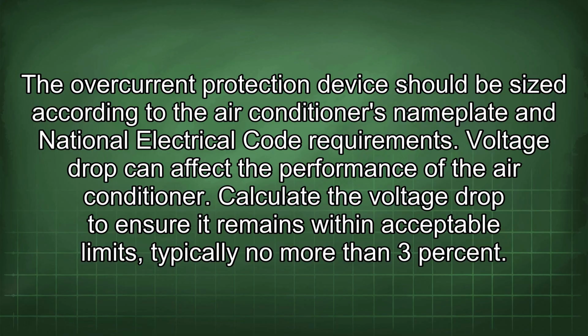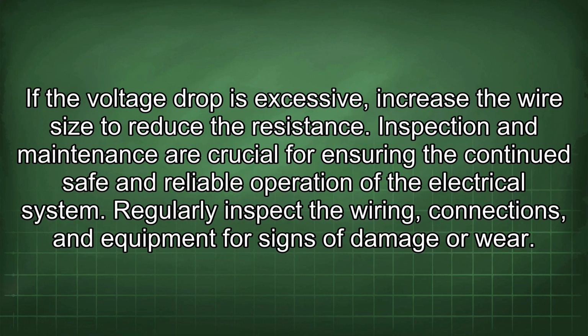Voltage drop can affect the performance of the air conditioner. Calculate the voltage drop to ensure it remains within acceptable limits, typically no more than 3%. If the voltage drop is excessive, increase the wire size to reduce the resistance.